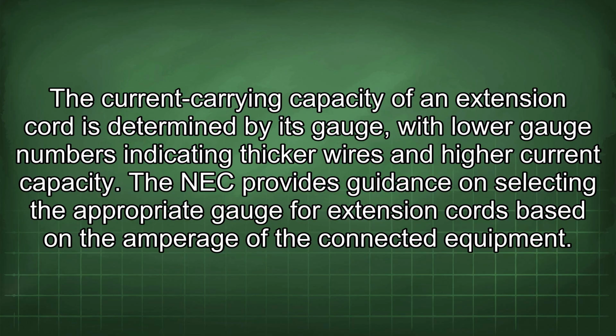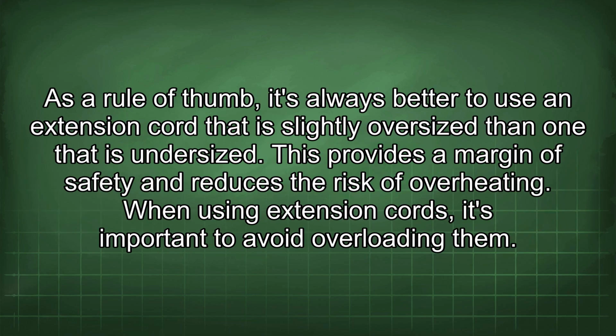The current carrying capacity of an extension cord is determined by its gauge, with lower gauge numbers indicating thicker wires and higher current capacity. The NEC provides guidance on selecting the appropriate gauge for extension cords based on the amperage of the connected equipment. As a rule of thumb, it's always better to use an extension cord that is slightly oversized than one that is undersized. This provides a margin of safety and reduces the risk of overheating.